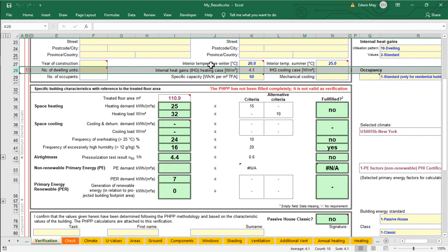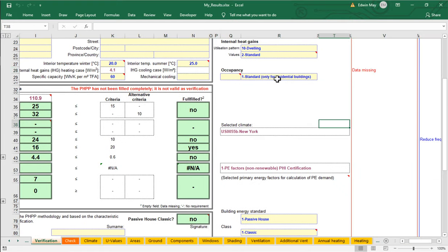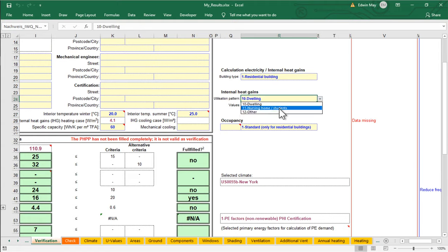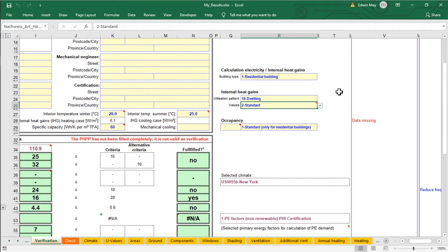The important data we're missing is the number of dwelling units. That's going to be one of the key inputs PHPP needs to calculate occupancy. Scrolling right on the verification worksheet, we also see a 'data missing' flag. On this same worksheet we can set the type of building — is it a residence or non-residence, a dwelling, hospital, nursing home, or dormitory? We also need to choose what type of internal heat gains values to use — standard or a custom detailed calculation.